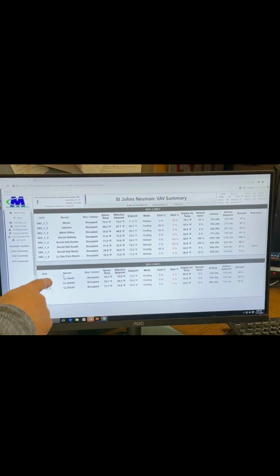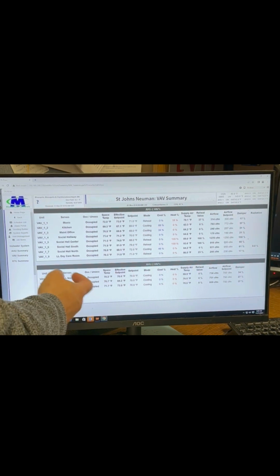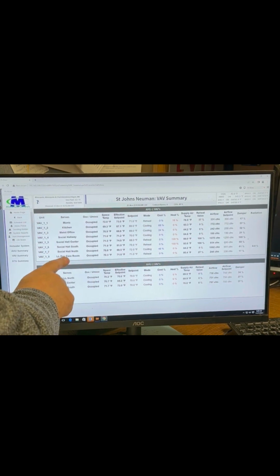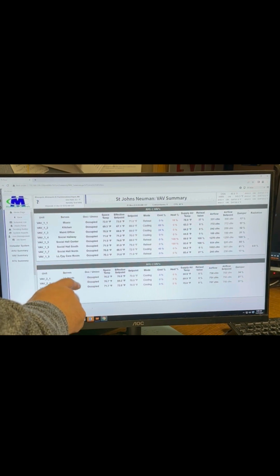We did replace the first 25 ton, Dan, that was this area. The second 25 ton dealt with these areas. And the RTUs are self-contained. What's condensing this unit? Why is that one separate from here? I think it's a rooftop. Nope. That's a VAV, and it's served by AHU 1. And the question is why, when everything else down there is. It's probably just the way the ductwork worked, is my guess. Okay.